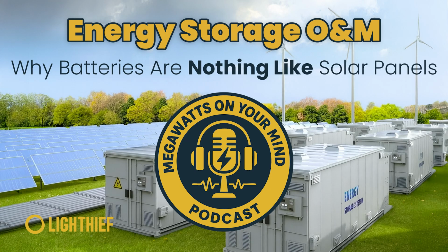An energy storage system requires two parameters: power and capacity. Power, measured in megawatts, is how quickly the storage can charge or discharge. Capacity, measured in megawatt hours, is how much energy the storage can hold. It's like a car. You need to know both the engine power and the fuel tank size to understand what it can do. Practical example, a 10 megawatt, 20 megawatt hour storage system. What does this mean? The system can discharge at 10 megawatts for 2 hours, or at 5 megawatts for 4 hours, or at 20 megawatts for 1 hour if the electronics allow it.